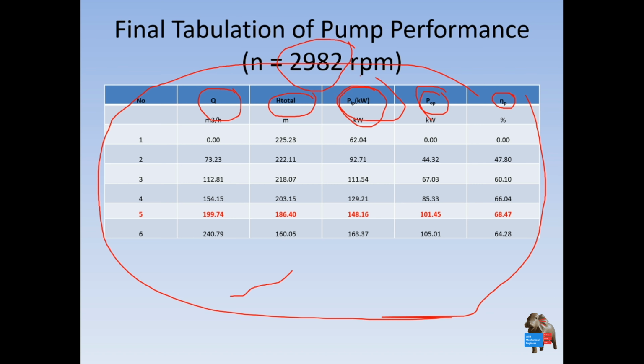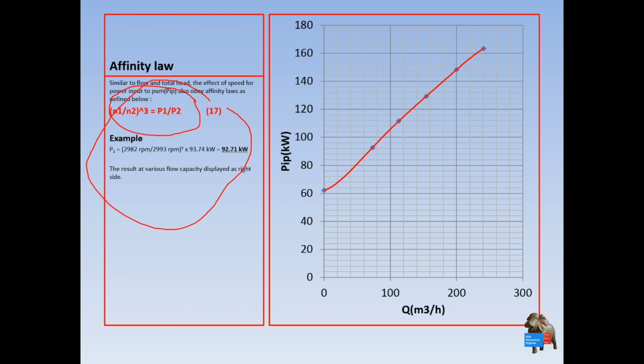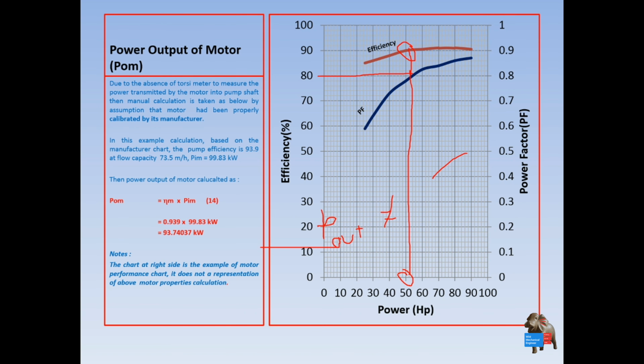If you compare the power output of the pump divided by the power input of the pump, you have the pump efficiency. But how do you calculate the power input to the pump? As you know, before we called it power motor in and power motor out. Power motor in, you measure with this power meter and multiply by the motor efficiency, and you have the power motor out. If you don't consider the losses inside the coupling, you can directly say that the power output of the motor will be the power input to the pump.